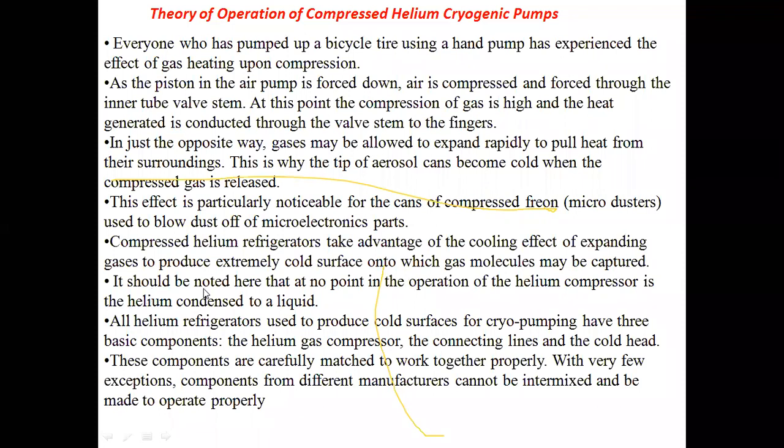It should be noted here that at no point in the operation of the helium compressor is the helium condensed to a liquid. That means at any stage of the operation, helium will not be condensed into a liquid state. It just expands and makes the surface cold. That is the idea behind it.